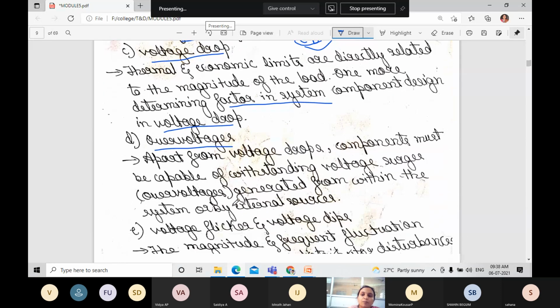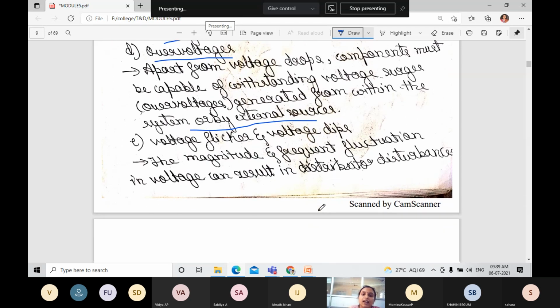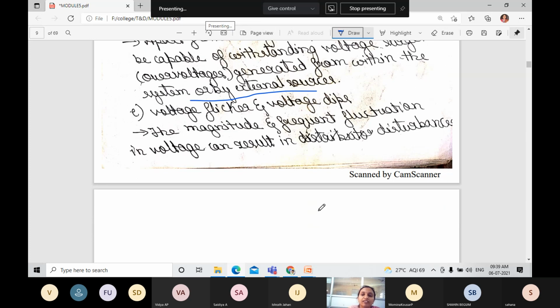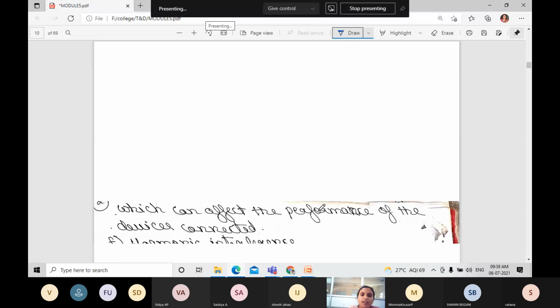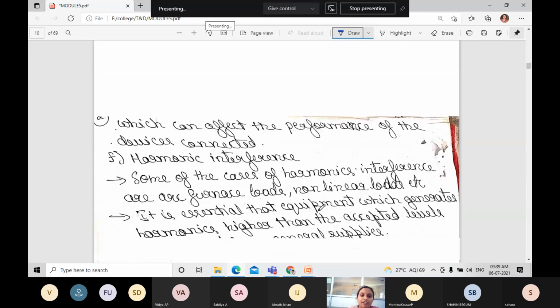Next, overvoltages. Apart from voltage drop, components must be capable of withstanding voltage surges. That is the plus or minus I mentioned: minus for voltage drop, plus for overvoltage. Any equipment or component will be given a plus or minus tolerance. Components must withstand voltage surges generated from within the system or by an external source. Next are voltage flicker and voltage dips. The magnitude and frequent fluctuation in voltage will result in a disturbance which can affect the performance of connected devices.